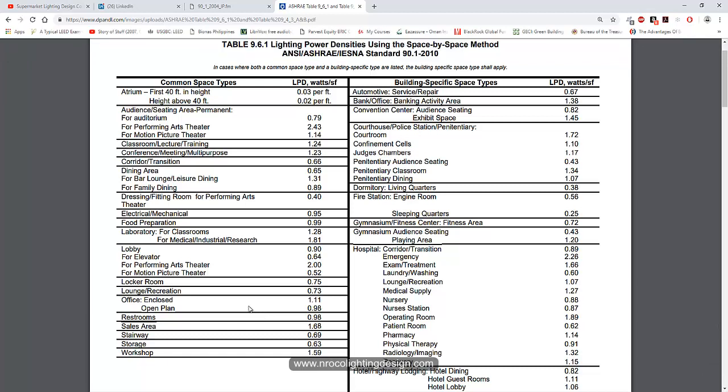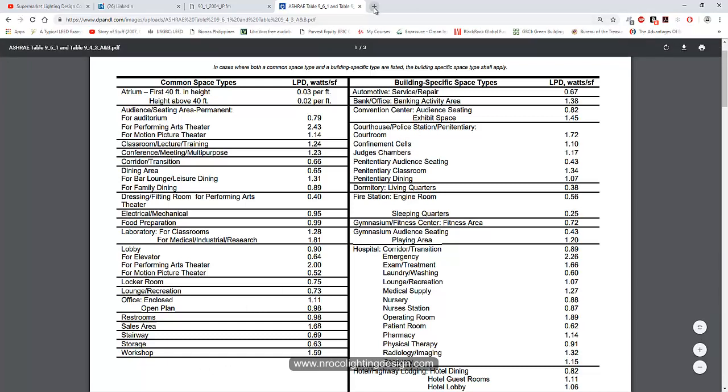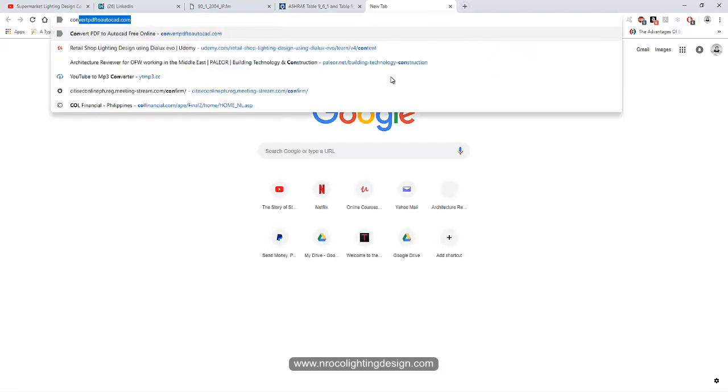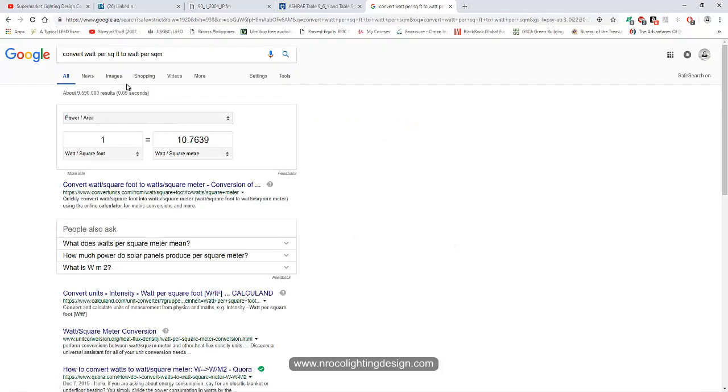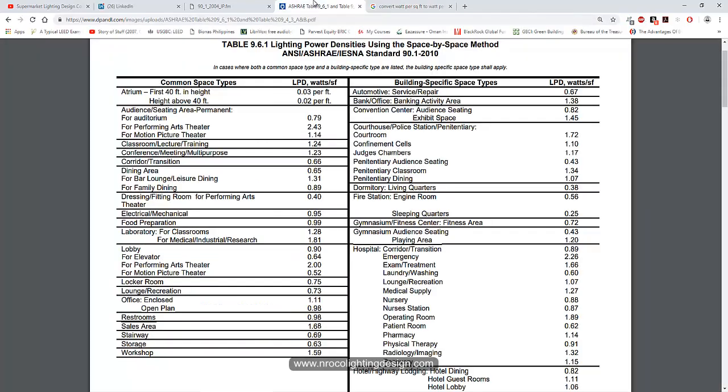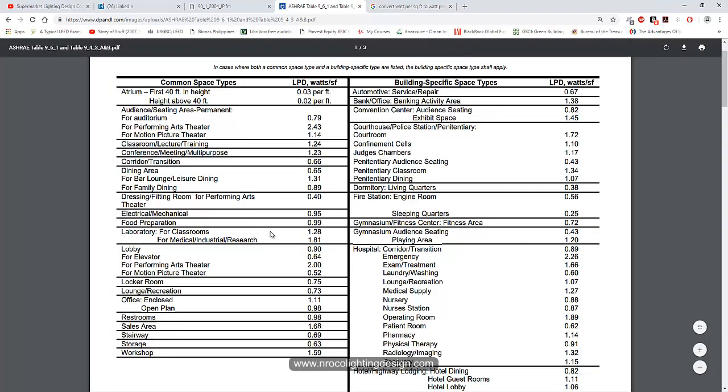You can just type 'convert watts per square foot to watts per square meter.' One watt per square foot equals about ten watts per square meter. For example, the LPD requirement for an open office is 1.1. You need to find this in your lighting calculation.